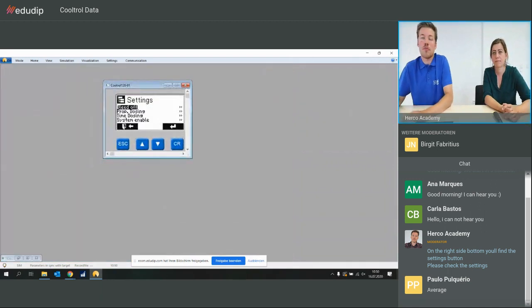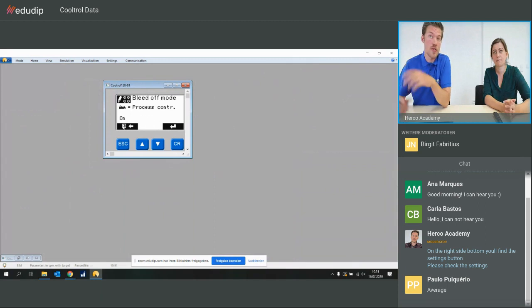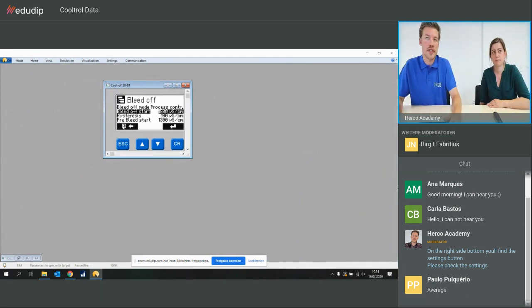All right. So, like I said, bleed off. There's all the information for the actual bleed off process. So we can say inside how we want to control it. This is the thing I told you that is new. You can either say process controlled, off, or on. Previously it was automatic, off, on, manual, or anything. So it's kind of reduced a bit, so it's more simple to understand. And we can say when we want to start the bleed off. So this is our working point where the valve opens and drains water from the system.